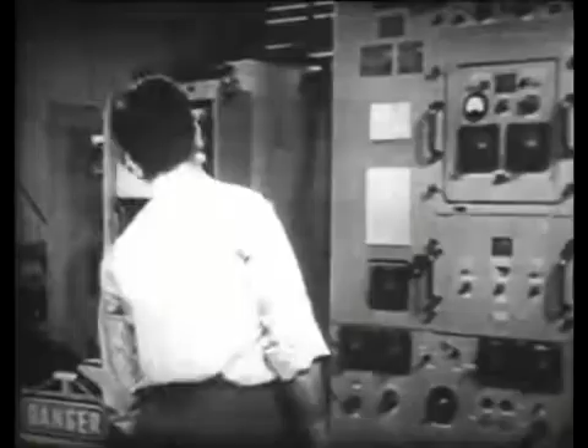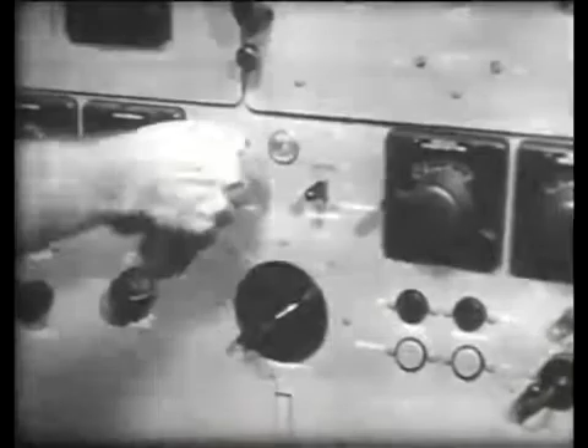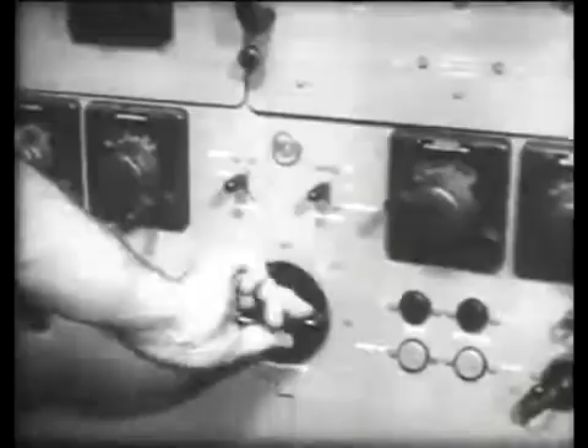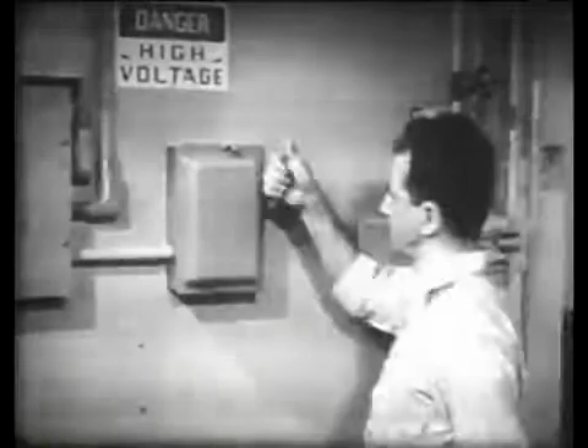We have shown the safe procedure for de-energizing equipment which is merely plugged into the electric power source. But where equipment is permanently wired in, additional precautions must be taken. Be sure to turn off the switches on the panel. And don't forget any switches that might cause the equipment to be controlled from some remote location. Then open the main supply switch and always be sure to tag it.